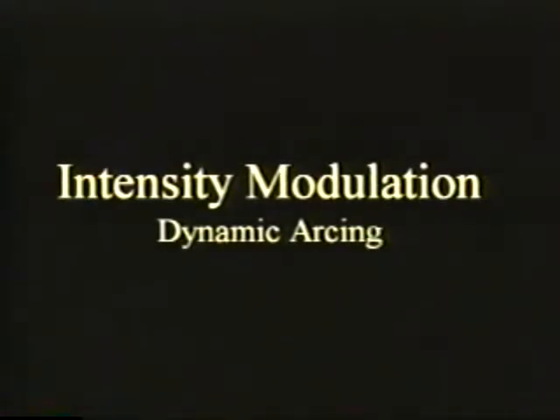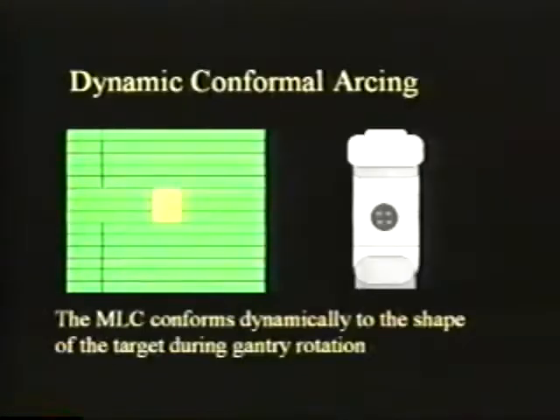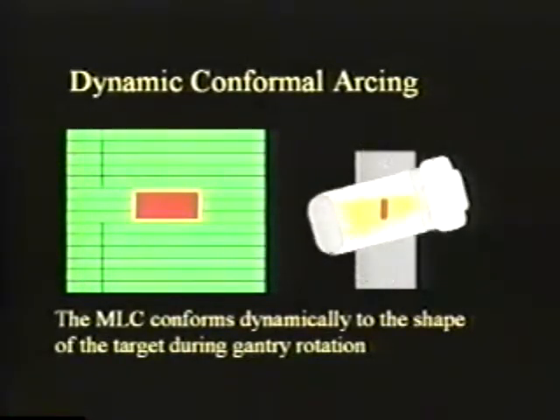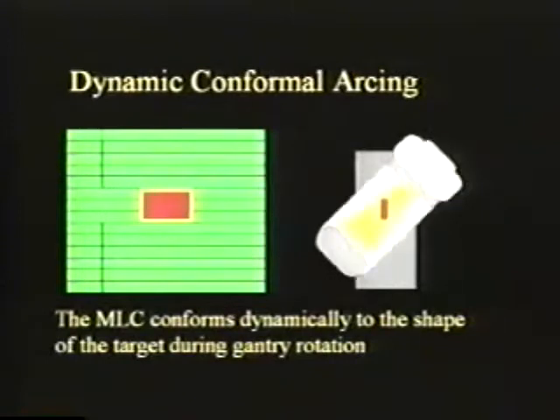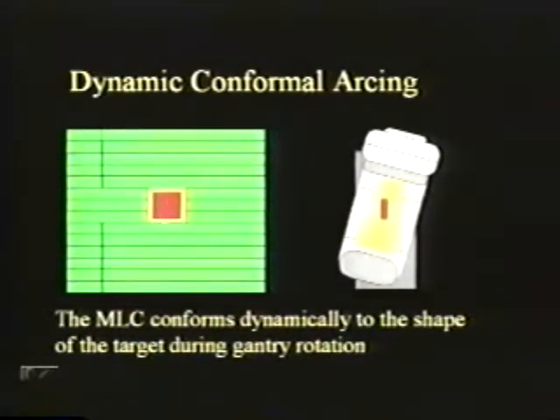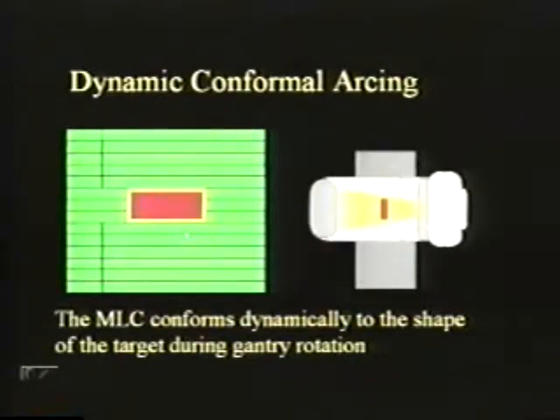The next type of intensity modulation delivery is dynamic arcing. The next two techniques now involve the linear accelerator rotating around the patient and modulating the beam. In conformal dynamic arcing, you have a target volume that is in the patient. Let's say a prostate, for example. And during conformal dynamic arcing, the radiation beam turns on, and the gantry rotates around the patient with the MLC leaves continually conforming to the shape of the target, which is this red block, from each gantry angle.